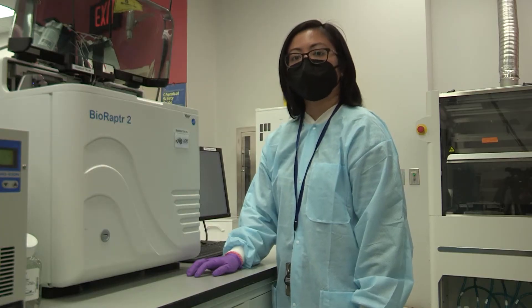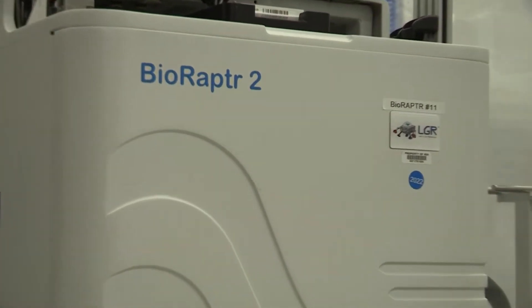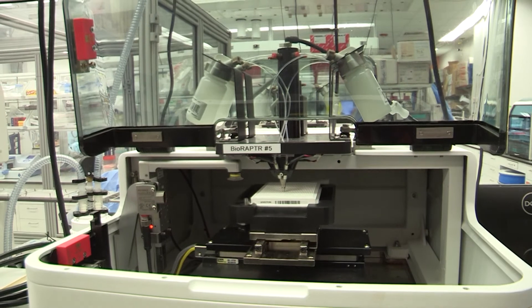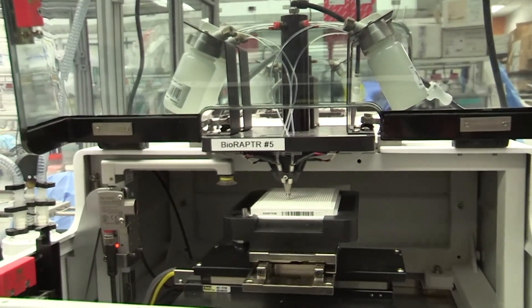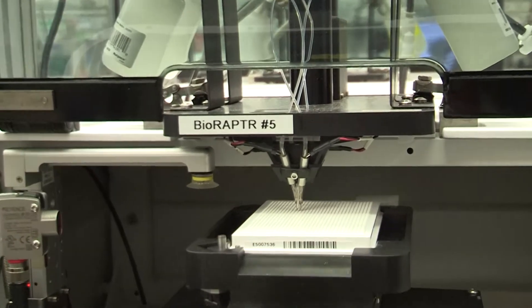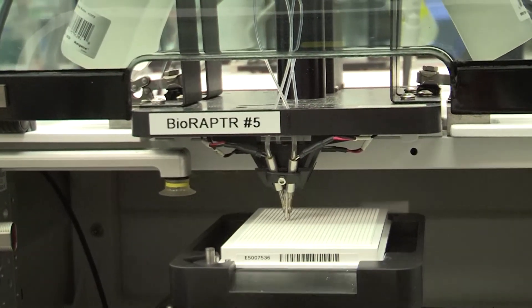The BioRaptr 2 Flying Reagent Dispenser, or FRD, has a four-chip piezoelectric dispensing system. It can dispense up to four reagents simultaneously and can fill a 1536 well plate in under a minute. This instrument is really great for enzyme assays and whole well reads.